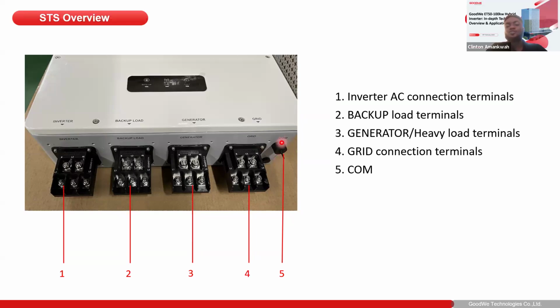is where you connect your communication cable between the STS unit and the inverter unit. So if you can recall, the inverter unit had a communication port labeled STS. So from the STS port on the inverter unit to the COM port of the STS unit, that's where you establish the communication between the STS unit and the inverter unit itself.